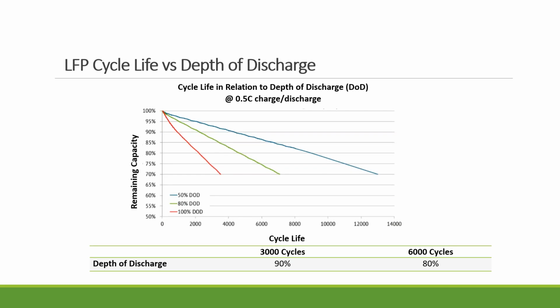And the third factor is the depth of discharge. That means how often you let the battery discharge. Starting with the blue here, if you set it up at 50% depth of discharge, it can go above 10,000 cycles. If you set it at 80% depth of discharge, you can go above 6,000 cycles. And if you fully discharge every time, from 100 to 0 and then back to 100 and so forth, that's really going to shorten the lifespan of the battery. You're looking at about 2,000-some cycles. And we guarantee 80% at 6,000 cycles.